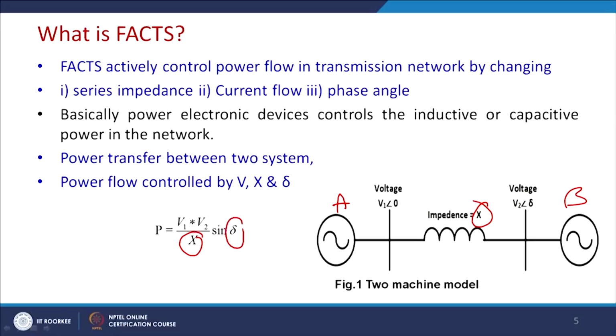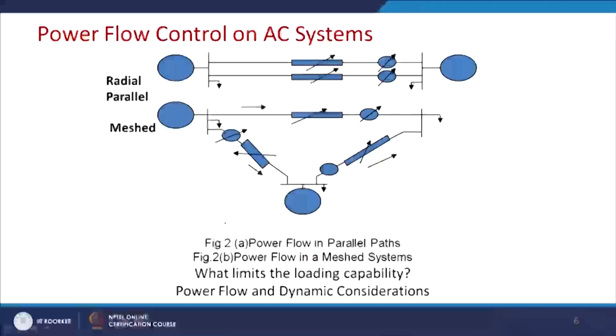Moreover, it can change delta and control the power flow through this line. Thus, in a series compensated transmission line, it can change the series impedance, it can change the power angle, and thus it can control the flow of current from point A to point B. Now, let us take a typical example. The upper one is a radial parallel system and the other is a mesh system. These impedances are basically series impedances, which can be actively controlled by these FACTS devices, and these are basically series injections of voltage or phase angle, and thus power flow from point A to point B can similarly be controlled.